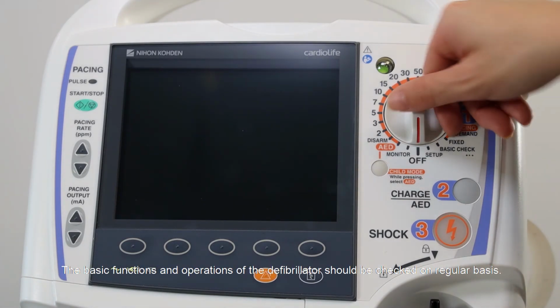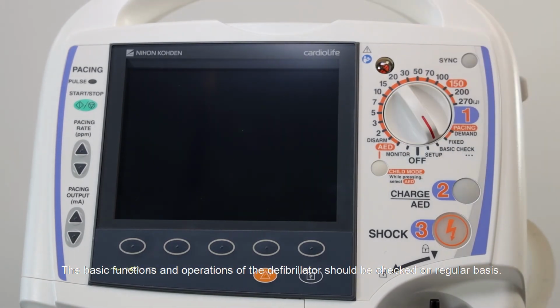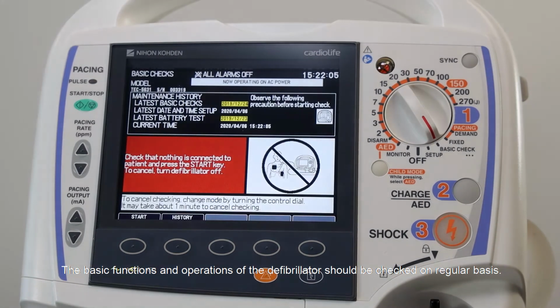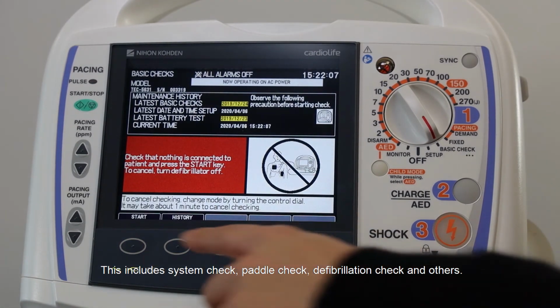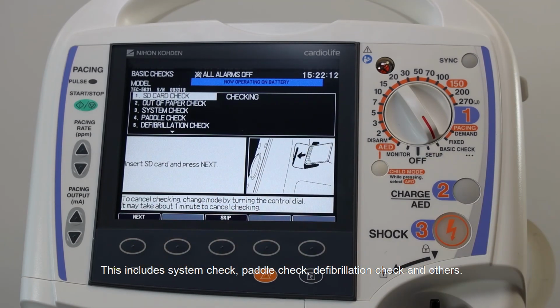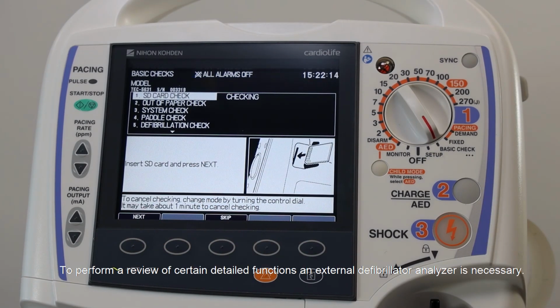The basic functions and operations of the defibrillator should be checked on regular basis. This includes system check, paddle check, defibrillation check, and others. To perform a review of certain detailed functions, an external defibrillator analyzer is necessary.